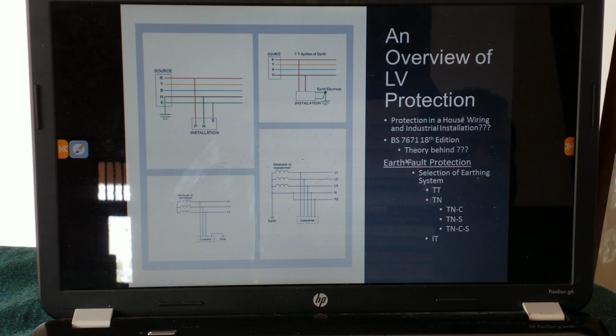This is earth fault. One of my main concerns is teaching you earth fault protection in the low voltage section, because almost all the problems I faced during my consultancy career were because of a lack of knowledge of earth fault protection. If you know exactly what an earth fault is, what the protection is, and what the solution is, we can solidly give a proper solution for several incidents. So let's think about this. Earth fault protection: before we choose a protection, we should choose the earthing system.